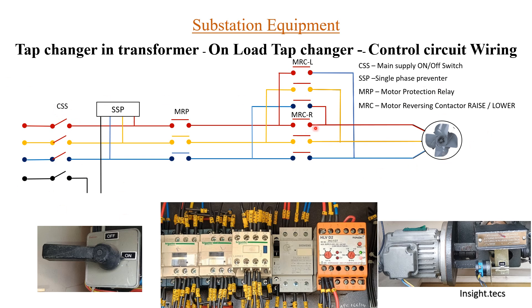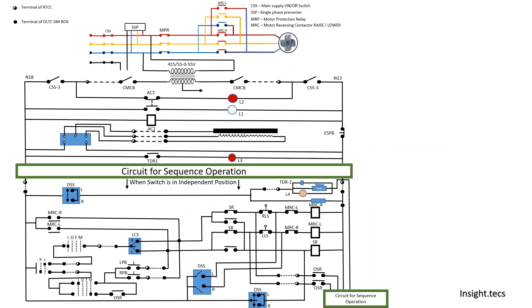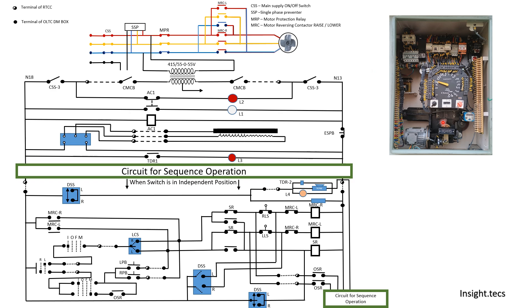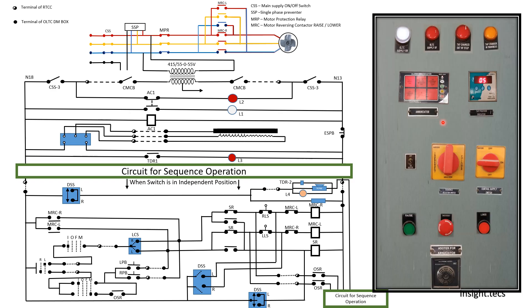Today we are going to learn in more detail about the control circuit wiring of this DM box and how its connection is done with the RTCC panel. In the previous video we saw the power circuit and how it helps the motor to rotate. This is the main CSS switch. Looking further into the control wiring — the DM box wiring and RTCC wiring — this is the control circuit explaining the connection between these two boxes.